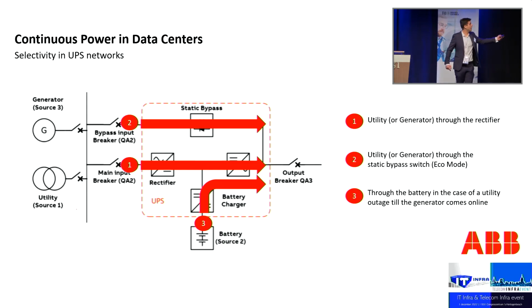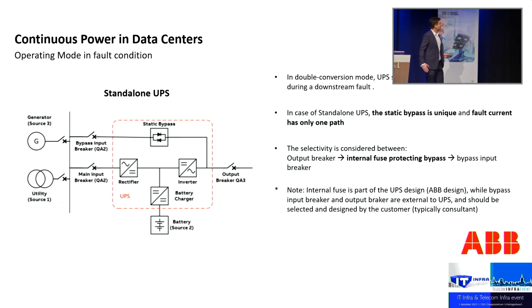And for me, for selectivity analysis, actually the second operation mode is the most interesting. And this is when I work on the static bypass, which is inside of the UPS. Why am I working on this device? It's because here we have thyristors, while in the rectifier and inverter we have IGBTs. IGBTs are much more sensitive components, much more sensitive to high currents, or better said, to higher energy, while thyristors can handle higher energy or higher currents for a longer time. For that reason, whenever I have a fault or any abnormal condition downstream of the UPS, my UPS automatically switches to the static bypass. And inside of this static bypass, there is an internal fuse, which is protecting it against those faults, of course, if the fault is too high or it's there for too long.